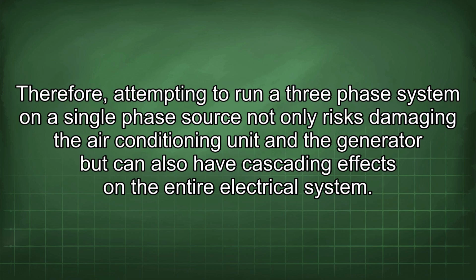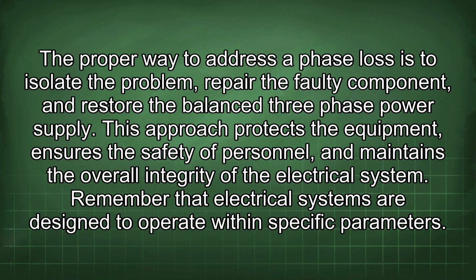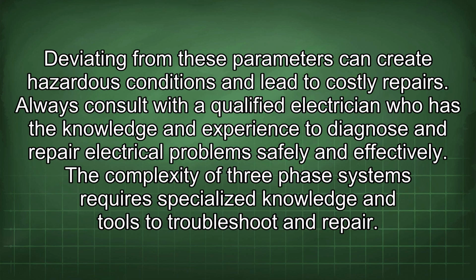Therefore, attempting to run a three-phase system on a single-phase source not only risks damaging the air conditioning unit and the generator, but can also have cascading effects on the entire electrical system. The proper way to address a phase loss is to isolate the problem, repair the faulty component, and restore the balanced three-phase power supply. This approach protects the equipment, ensures the safety of personnel, and maintains the overall integrity of the electrical system. Remember that electrical systems are designed to operate within specific parameters. Deviating from these parameters can create hazardous conditions and lead to costly repairs.